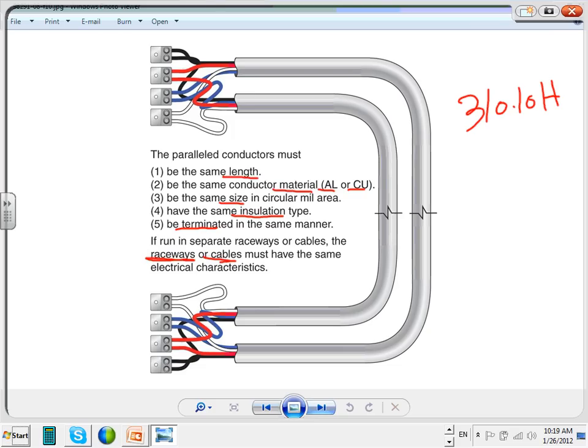And I'm going to add one more, so this will be 6 here, the raceway 7, and probably you guys know it, you cannot parallel smaller than 1/0, even if you want to. These are the rules for paralleling. Same insulation, same length, same material, same size, same termination. Termination means I can't have different lugs on the sides, and same raceway, and I can't parallel smaller than 1/0. Questions?